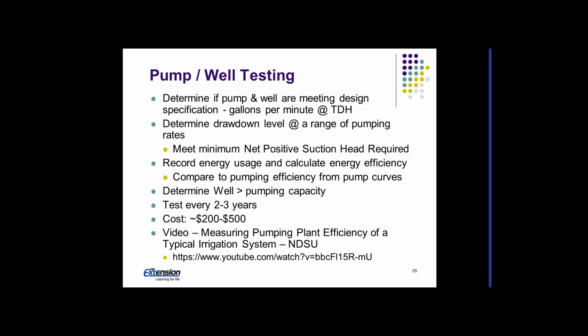In many cases, we're going to do an actual well test or a pumping test. This can be done by a contractor, or if you've got the right equipment, you can do it yourself. Typically, it's an open flow test, but it can be done with a pivot running as well. What we're going to determine is if the pump and the well are meeting the design specifications. So we're going to run a test. We'll look at the gallons a minute. We'll look at the dynamic feet of head, or dynamic total head, and see if it compares to when the pump was put in or when it was designed.